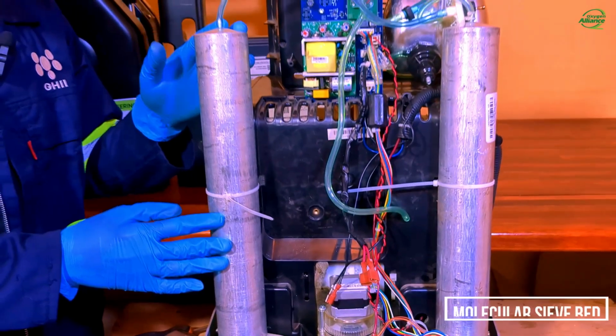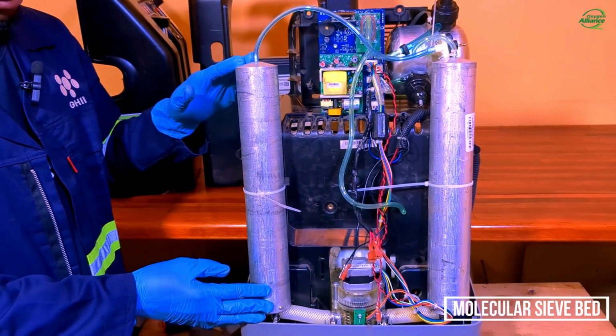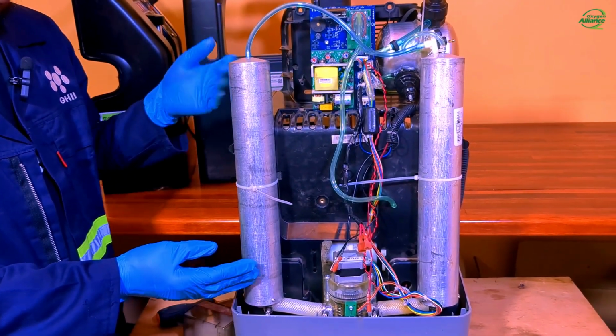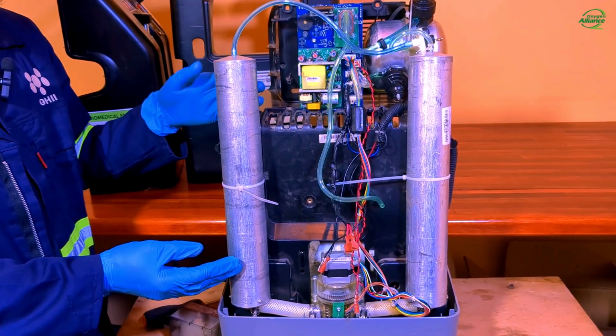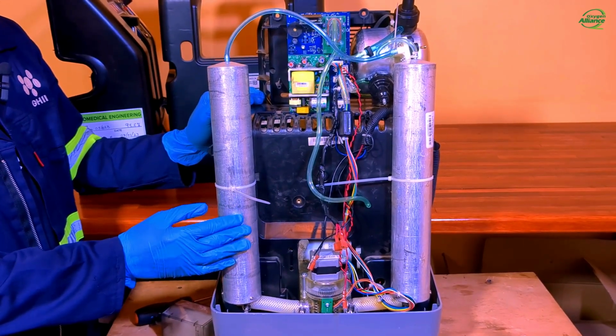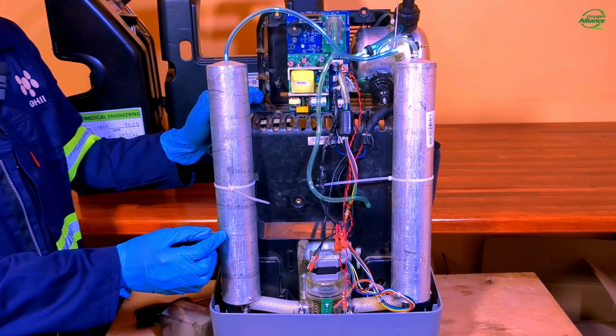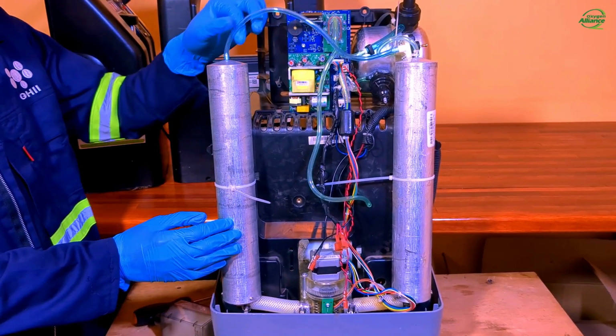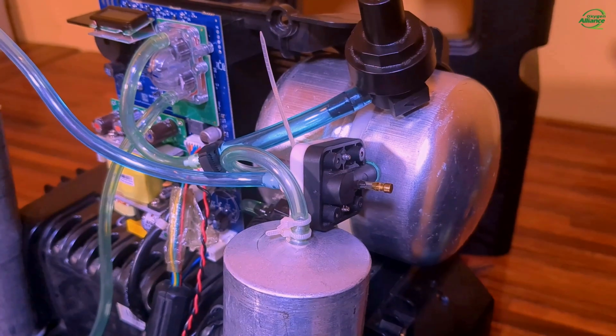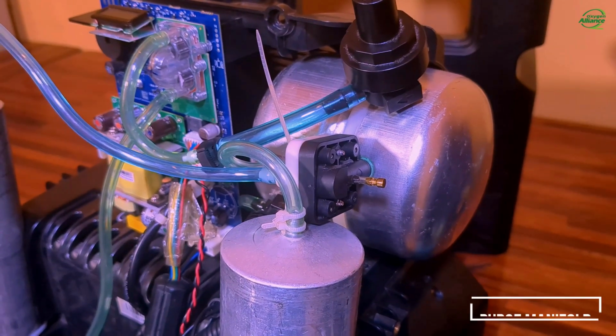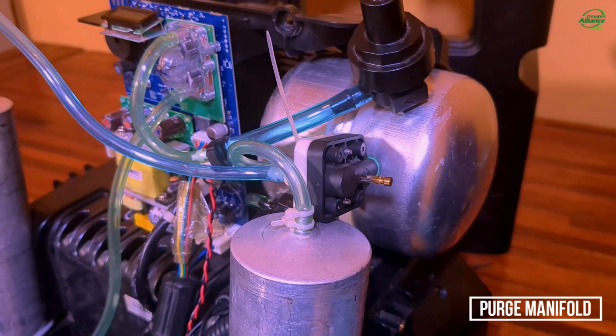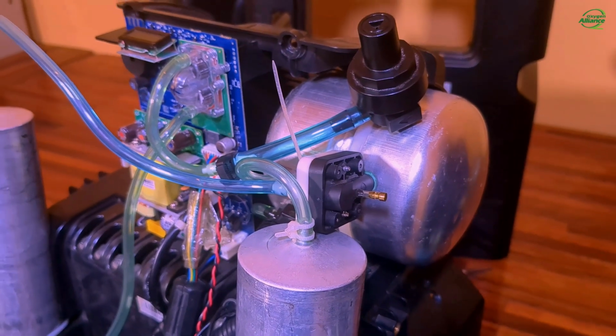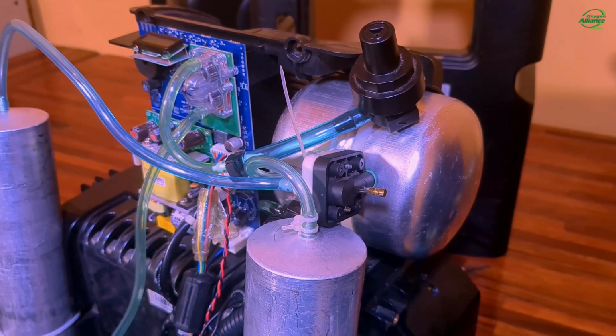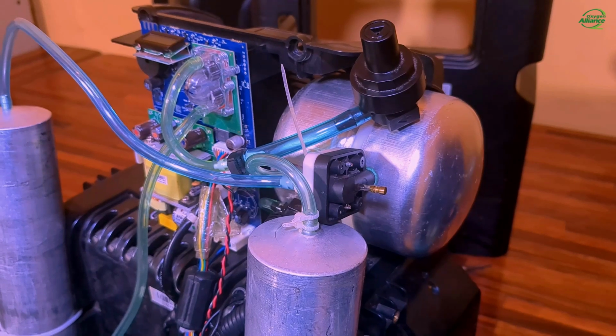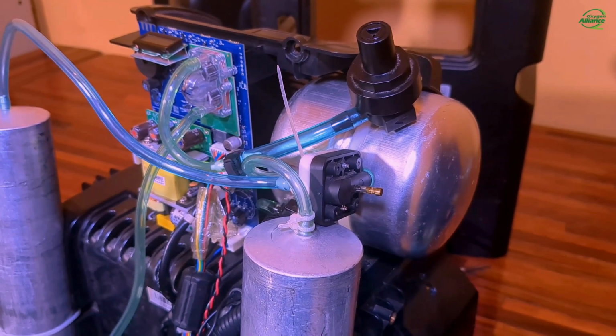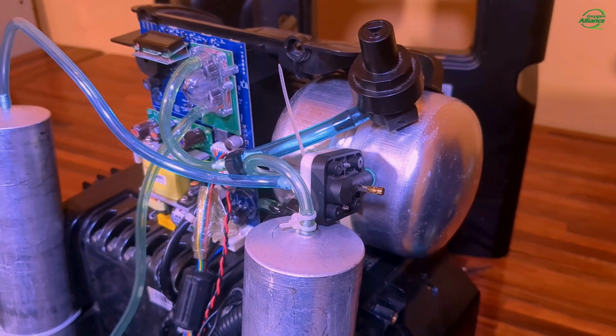Now this is the sieve bed. The molecular sieve bed, usually made out of aluminium, contains a substance known as zeolite. Zeolite filters out nitrogen, thereby allowing concentrated oxygen to pass through the outlet. So moving on, I will explain about the purge manifold. So that is this part right here. And what this part does is, it helps to purge out nitrogen in the depressurizing sieve bed. This part also contains check valves, which are there to prevent the backflow of oxygen from the product tank to the sieve beds.